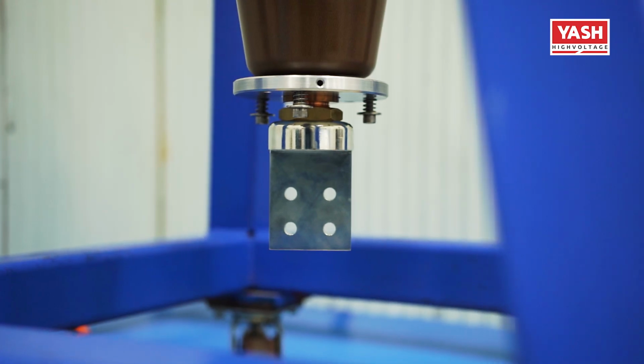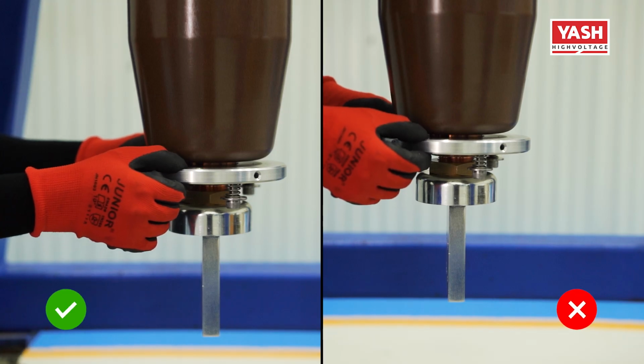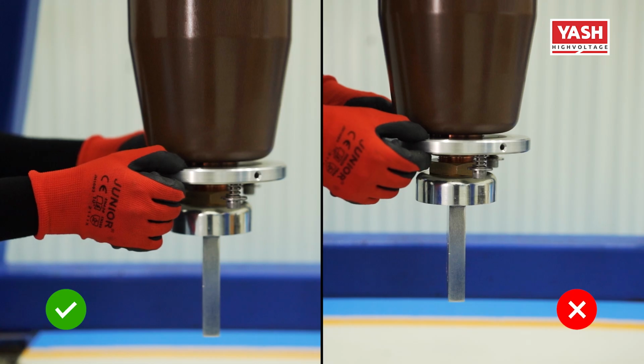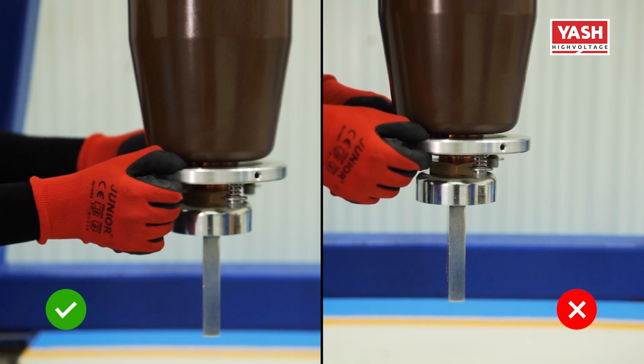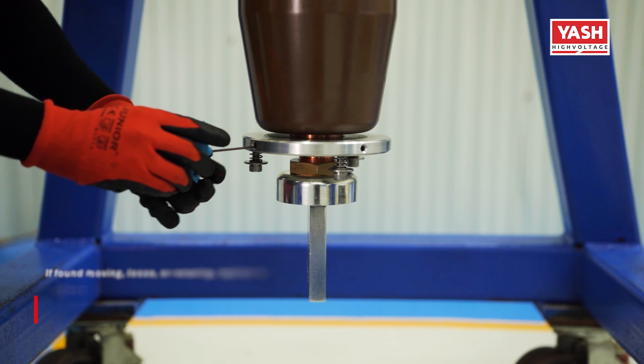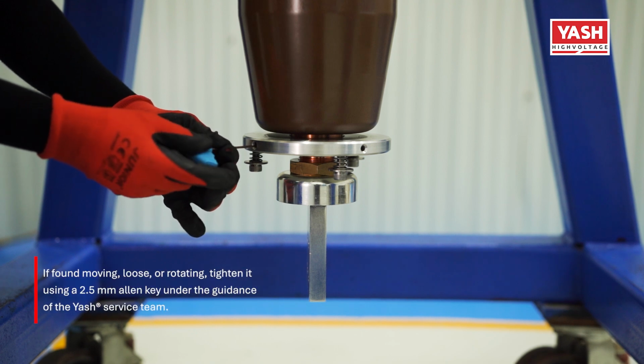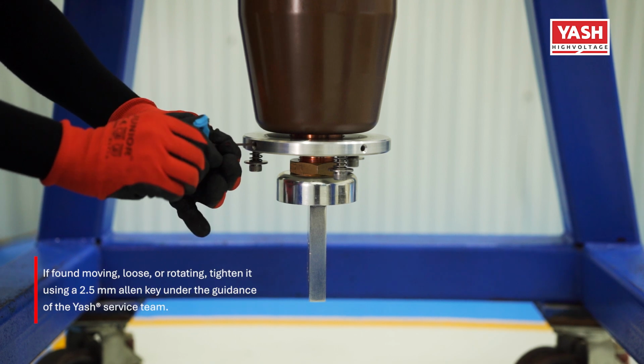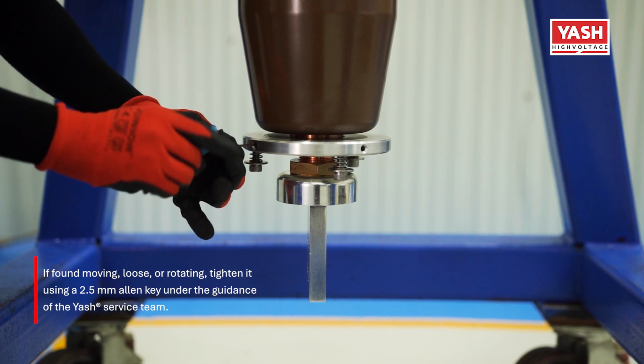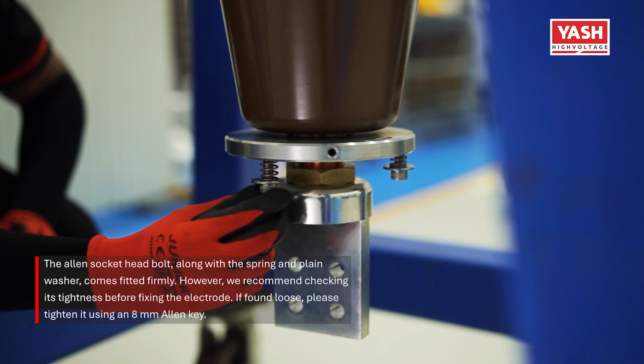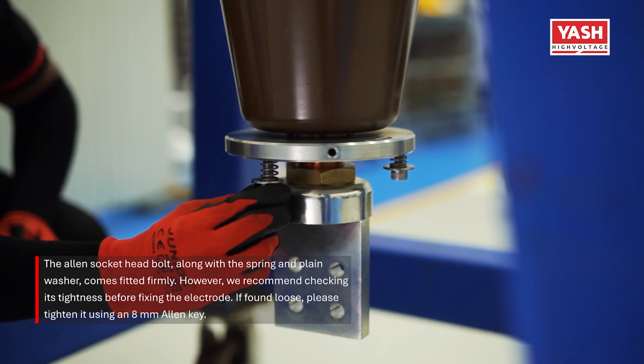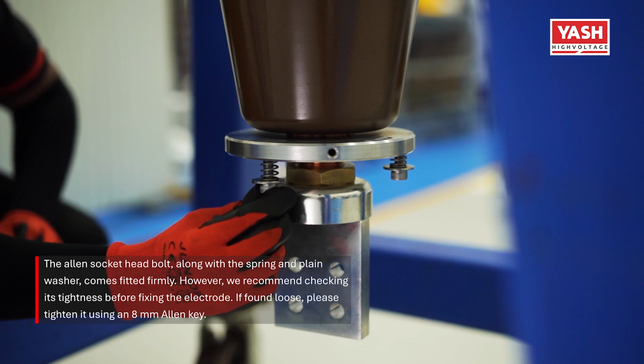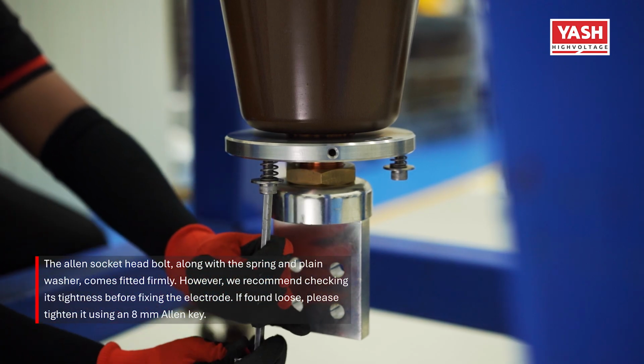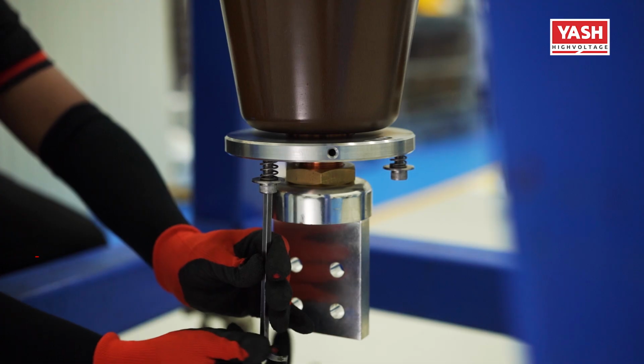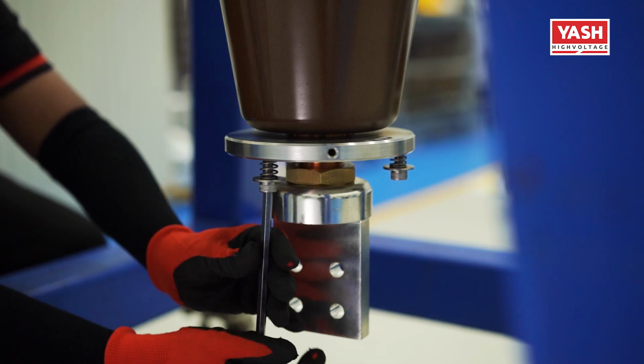Before attaching the bayonet electrode, ensure that the electrode support is properly secured and firm, without any movement, rotation or looseness. If found moving, loose or rotating, tighten it using a 2.5 mm Allen key under the guidance of the Yash service team. The Allen socket head bolt along with the spring and plain washer comes fitted firmly. However, we recommend checking its tightness before fixing the electrode. If found loose, please tighten it using an 8 mm Allen key.